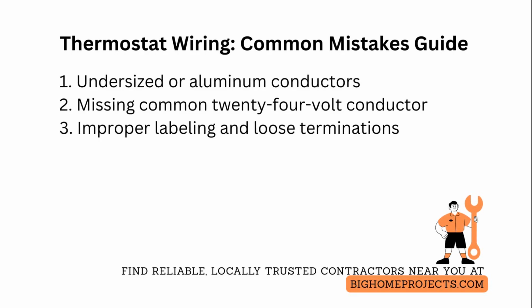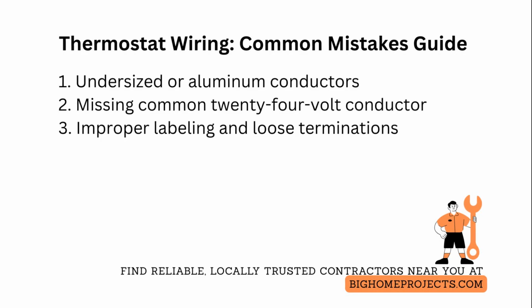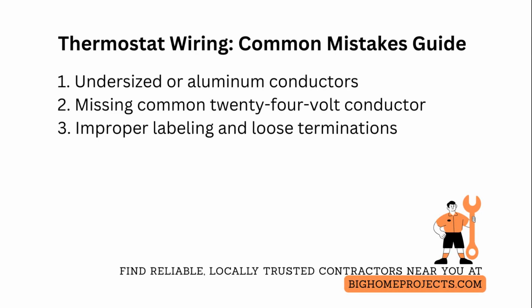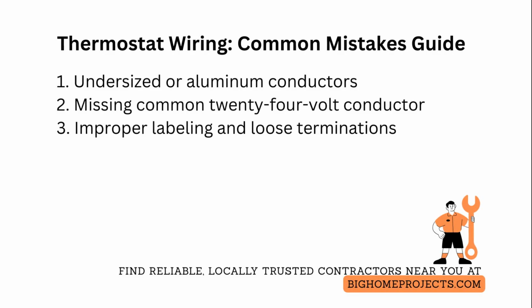The third frequent issue is improper labeling and loose terminations that lead to intermittent compressor short cycling. Fix by labeling each conductor clearly, torquing terminals to spec, and performing a full system startup sequence to confirm correct staging.